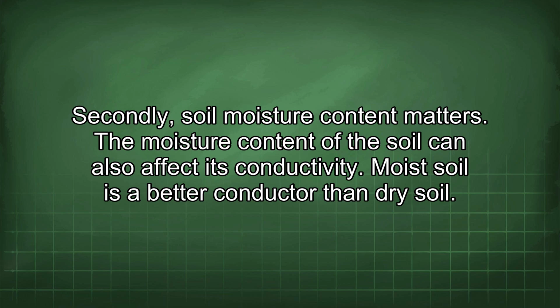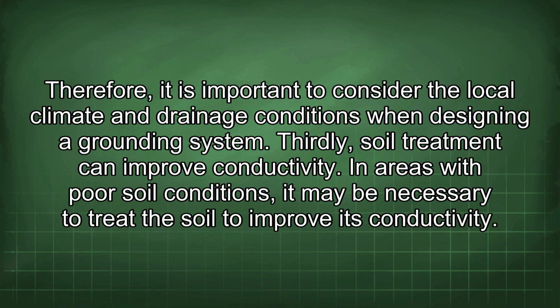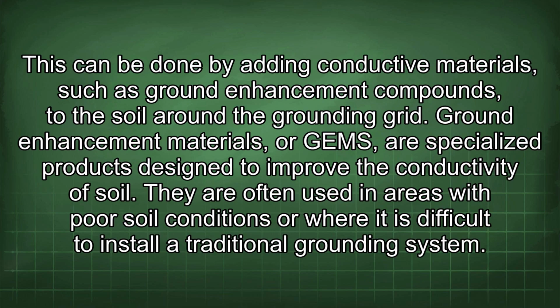The moisture content of the soil can also affect its conductivity. Moist soil is a better conductor than dry soil. Therefore, it is important to consider the local climate and drainage conditions when designing a grounding system. Thirdly, soil treatment can improve conductivity. In areas with poor soil conditions, it may be necessary to treat the soil to improve its conductivity. This can be done by adding conductive materials, such as ground enhancement compounds, to the soil around the grounding grid.